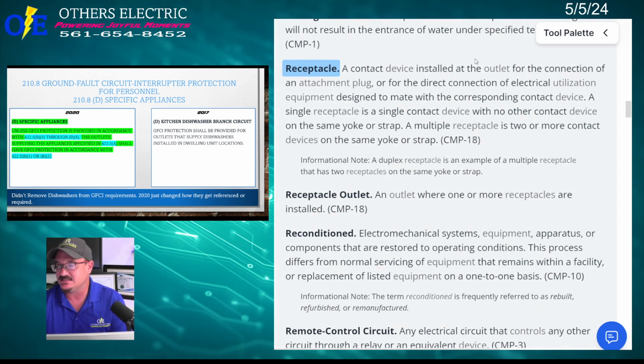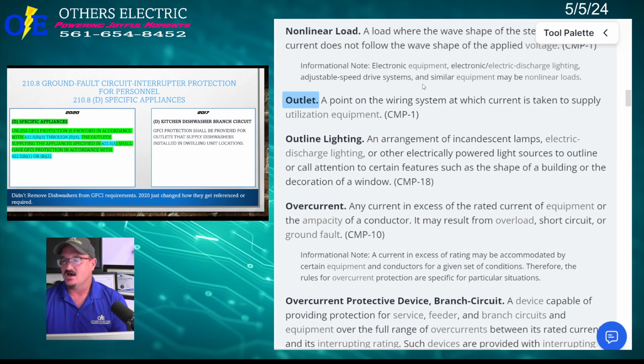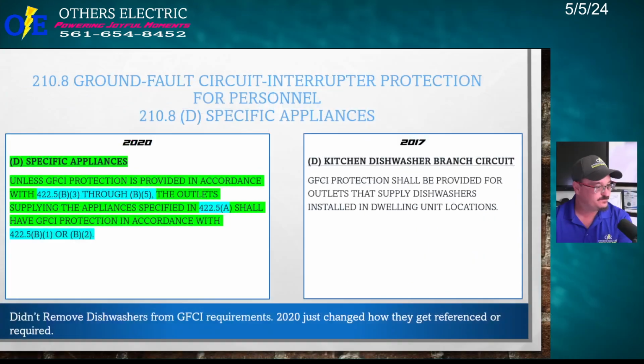So let's look at what the NEC calls an outlet. I didn't know this for the longest time. So this is why I want to tell you guys. Okay, so this is an outlet. An outlet is a point on the wiring system at which current is taken to supply utilization equipment. Utilization equipment is anything. Now it could be the receptacle, it could be the switch, it could be a light fixture, it could be a disconnect for a piece of equipment, it could be the box for the water heater. Where you get the electrical source from, that's the outlet. So now we're talking about outlets, okay? So I just wanted to point that out.